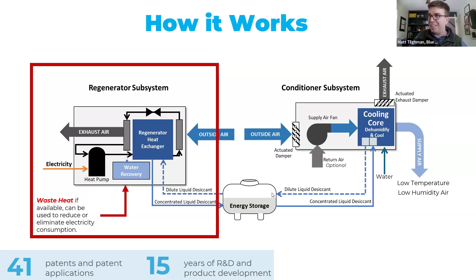But since it's a thermal process, you can also run this on waste heat. And we have a lot of people that are pushing us towards that for reasons like running this on the waste heat of a generator during a disaster, running it on the waste heat of a heat rejection chiller because they don't know what to do with their waste heat, stuff like that. But GTI, Gas Technology Institute, has done research and published a paper on our regenerator using waste heat. And it had a thermal COP of about 0.8 to 1 between the temperatures of 60 Celsius and 80 Celsius.